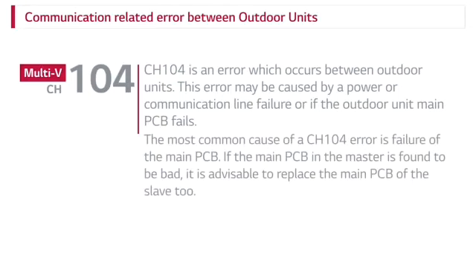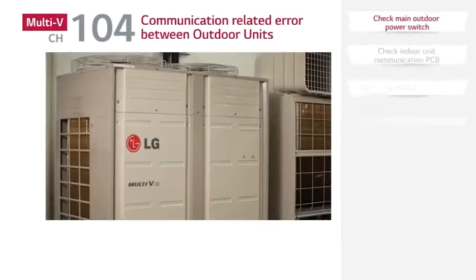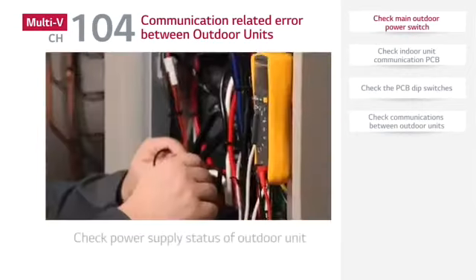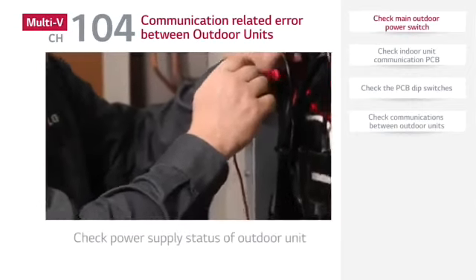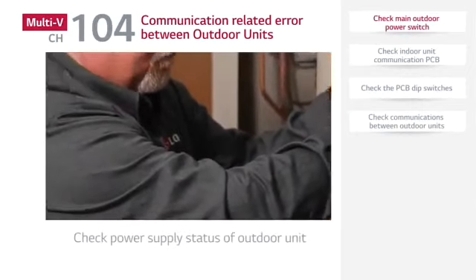The most common cause of a CH104 error is failure of the main PCB. If the main PCB in the master is found to be bad, it is advisable to replace the main PCB of the slave too. First, check for proper power supply to the outdoor unit. The measurements of voltage between phases are as follows.